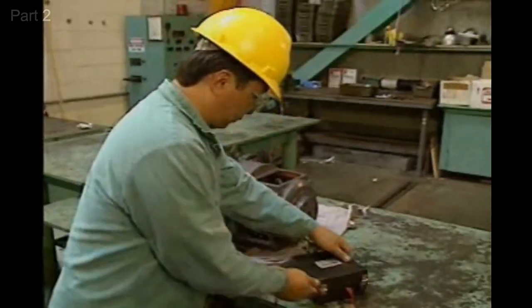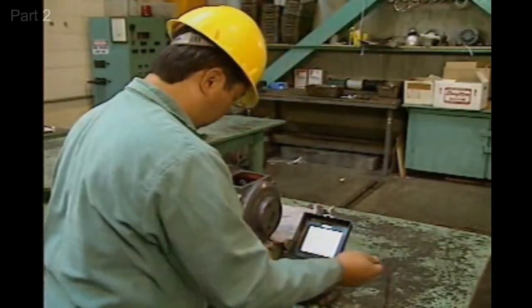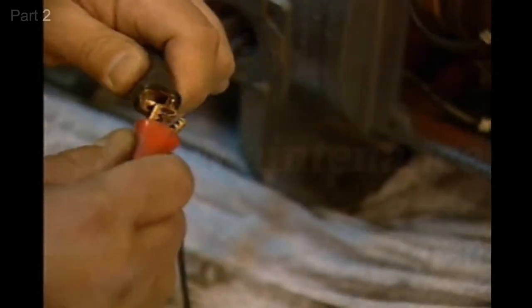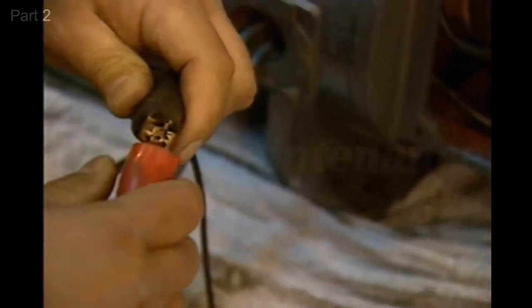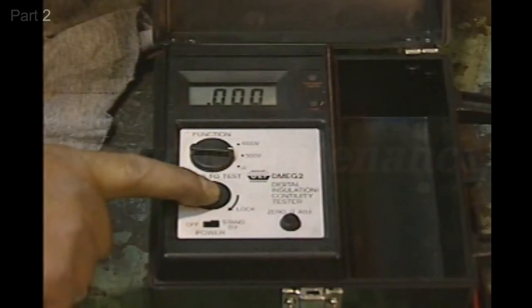Before a meg-ohm meter is used to test for grounds, it should be tested to make sure that it's operating properly. Begin by clipping the meter's two probes together and operating the meter. The meter should indicate zero resistance.